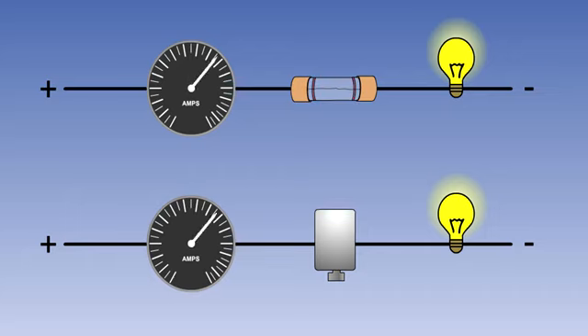A fuse will blow in a shorter time than it would take for a circuit breaker to trip. In both cases, the time taken is measured in fractions of a second, but this can be important for pieces of sensitive electronic equipment, which are often individually protected by fuses.